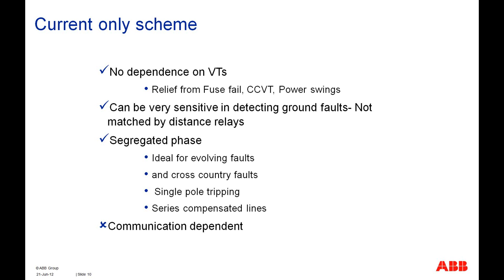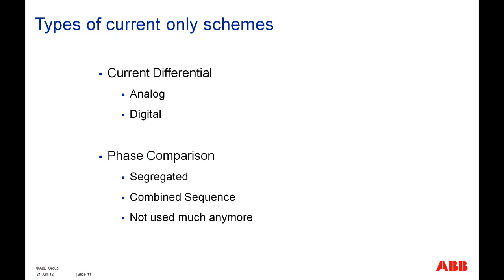But in high voltage or extra high voltage lines, of course, both of these protection schemes are used, with the main as line differential protection and the backup as distance protection. Types of current-only schemes: current differential can be analog or digital, and you can compare the phases as well, but that's something which is not really popular nowadays. So we will move on to the next slide.